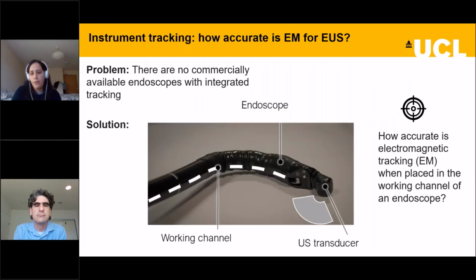But with EUS, we have a big problem, and that is that there are no endoscopes commercialized with integrated tracking. So having a look at the different options we had, we decided to use electromagnetic tracking, mainly because the endoscope is flexible and other systems such as optical tracking wouldn't work. So in electromagnetic tracking systems, we track small sensors that move within a field that is created by a field generator. There is no need to maintain a line of sight between the sensors and the field generator, which makes them very suitable to track instruments inside the body, such as endoscopes or needles.